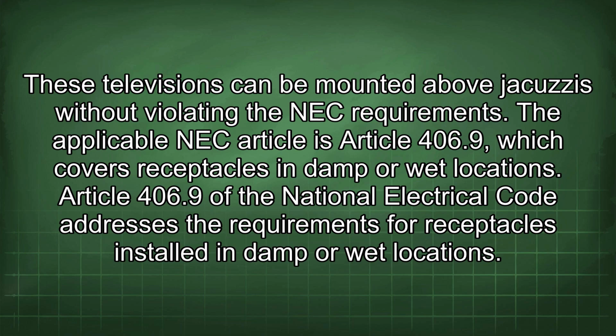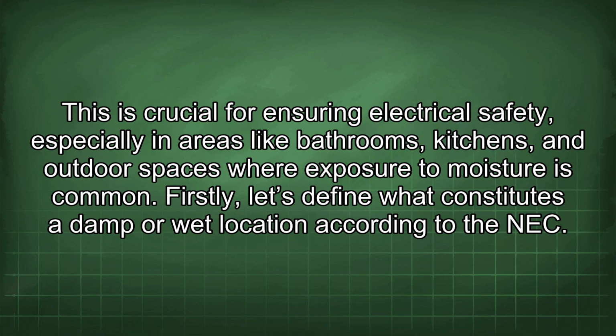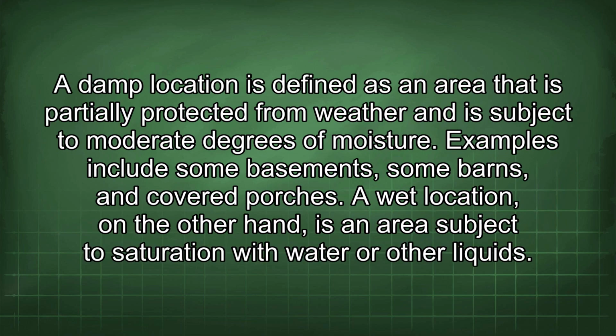Article 406.9 of the National Electrical Code addresses the requirements for receptacles installed in damp or wet locations. This is crucial for ensuring electrical safety, especially in areas like bathrooms, kitchens, and outdoor spaces where exposure to moisture is common. Firstly, let's define what constitutes a damp or wet location according to the NEC. A damp location is defined as an area that is partially protected from weather and is subject to moderate degrees of moisture. Examples include some basements, some barns, and covered porches.